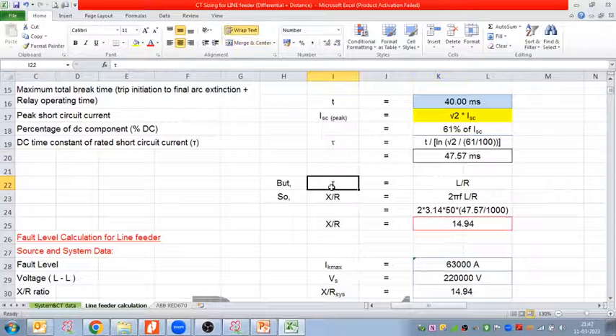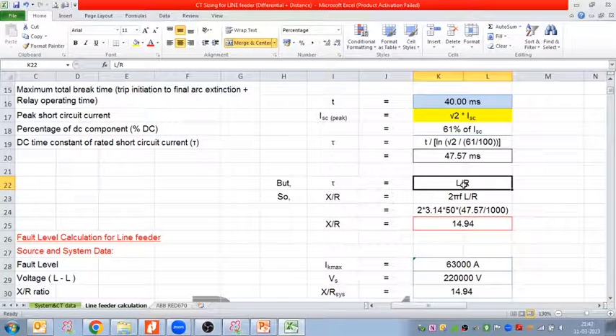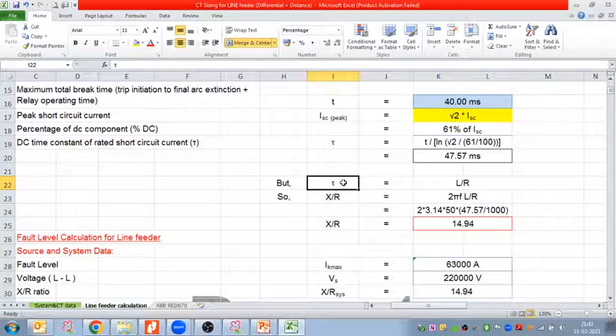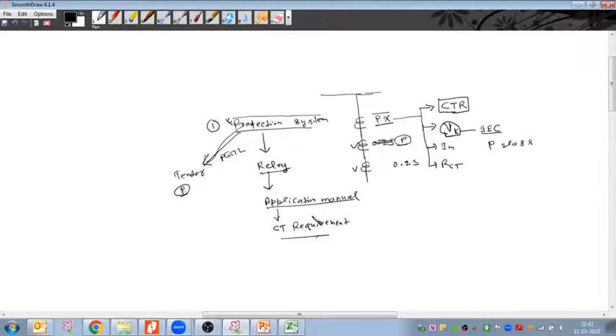Now we know that the time constant tau is equal to L by R, and we want to calculate the source resistance and reactance, X and R. So we know the tau we calculated, and tau is equal to X by R. X is 2 pi F L, divided by R, and tau is L by R, the time constant. So X by R is 2 into pi into F into tau. Tau is already calculated, so we can easily calculate the source X by R ratio.